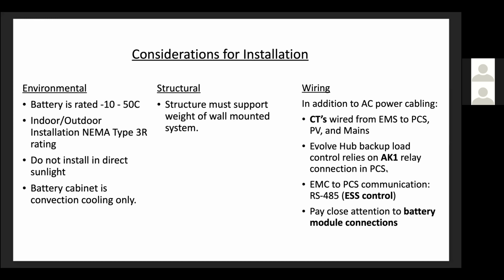And then there's an EMC to PCS communications for serial Modbus or its RS-485 connection for battery control. So pay close attention to the battery module connections, as I showed you in the DC architecture drawing. All of the LFP power conductor connections, as well as the communications connections, are very specific. So please pay attention to the instructions that are provided.